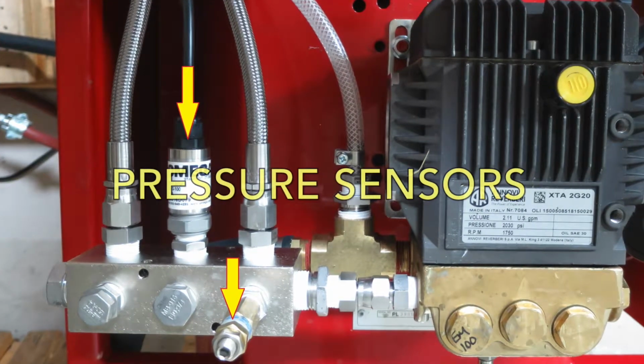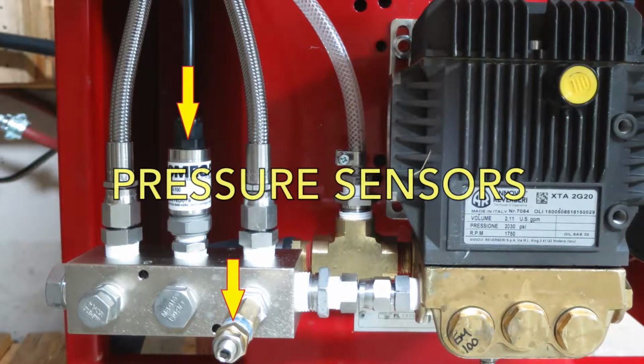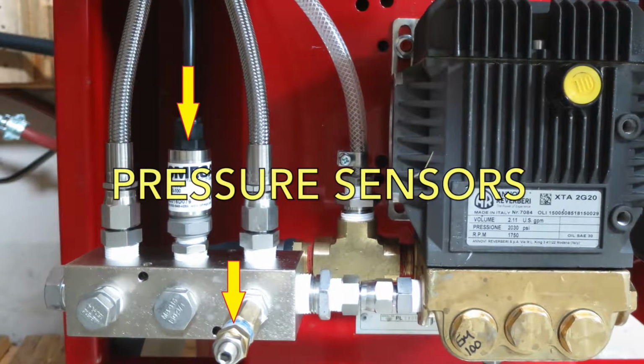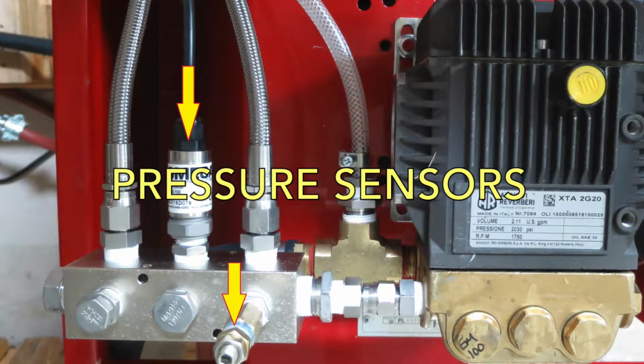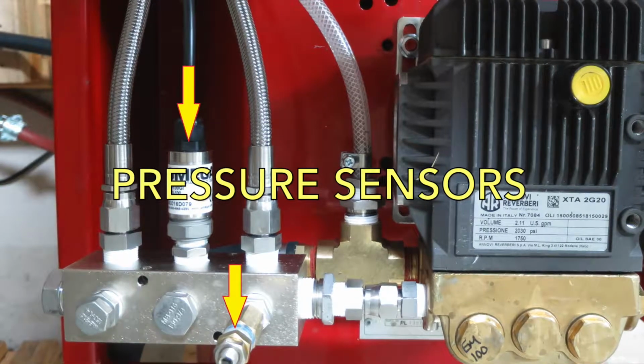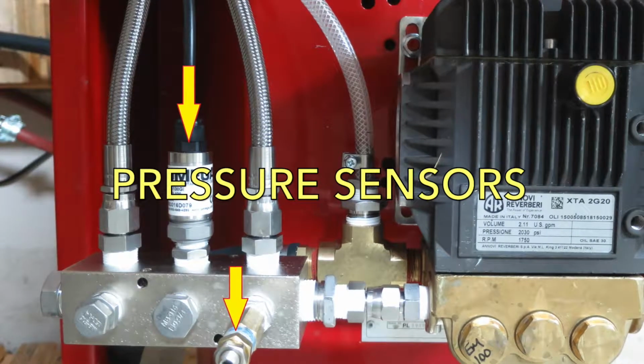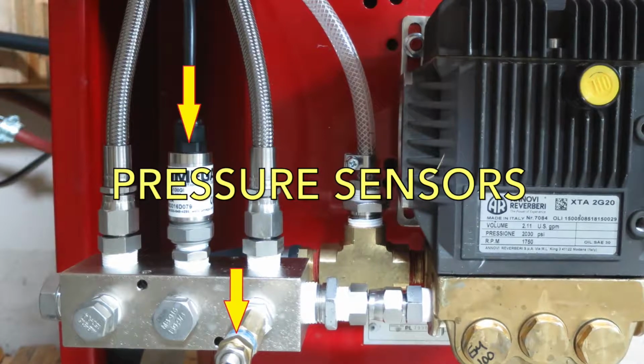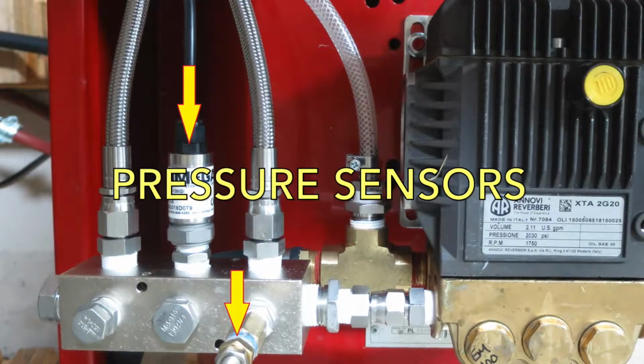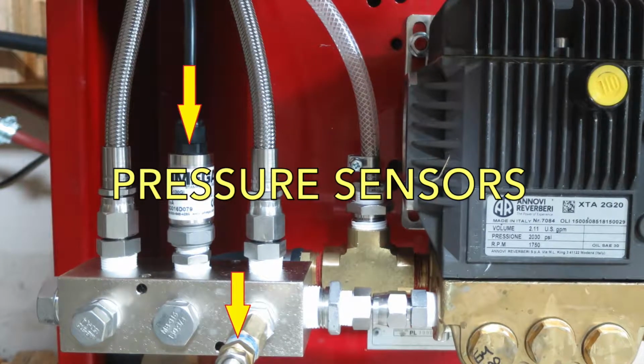The system pressure is monitored in the pumping circuit prior to entering the burner. It is essentially monitoring back pressure in PSI and is attached with the black wire to the front panel meter. The pressure sensor is located in the manifold next to the pump. The pressure relief valve is also located in this manifold.